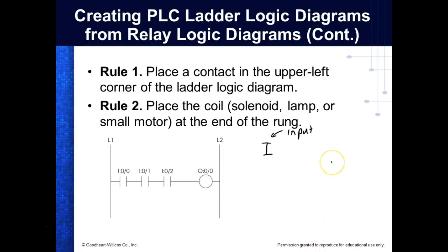So if I was to come up here and want to address, the syntax is we would put an I for input, one of our input ports, and then we'd put an O for one of our output ports. And these are what we call bit instructions. So we're dealing with a word, so Allen Bradley goes in words. Y'all understand that? So it goes in what? 16 bits. So as soon as I say input, we're addressing a 16-bit input port.